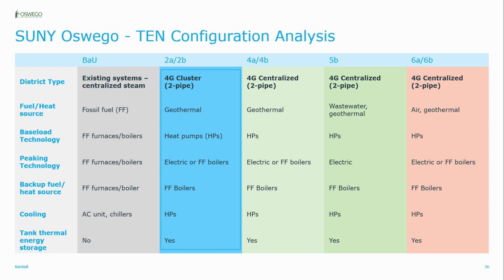In all cases we looked at base load and peaking, that chart we showed before about the 55-45 split, but then we looked at different peaking options, whether to go all electric with electric boilers or stick with existing fossil fuel boilers. In all cases we maintained those fossil boilers for backup purposes, so if the grid goes out or the heat pumps go out, you still have capability to produce heat. They are an area of refuge for the area in natural disasters, so they wanted to maintain that stability and reliability. Heat pumps would produce all the cooling in addition to existing chillers, and we looked at thermal energy storage for all cases.